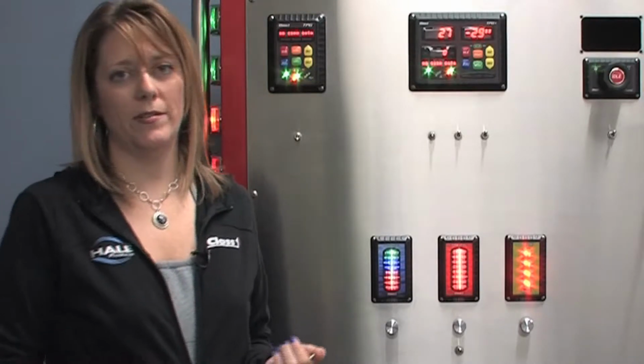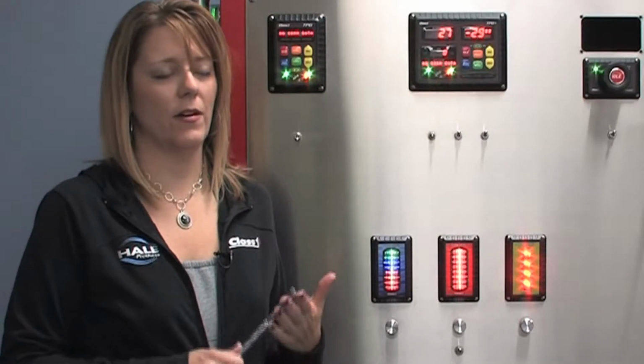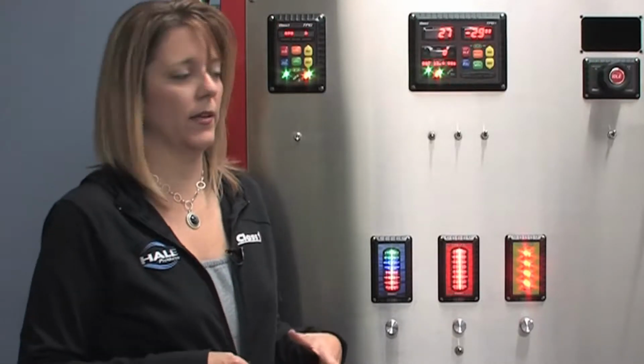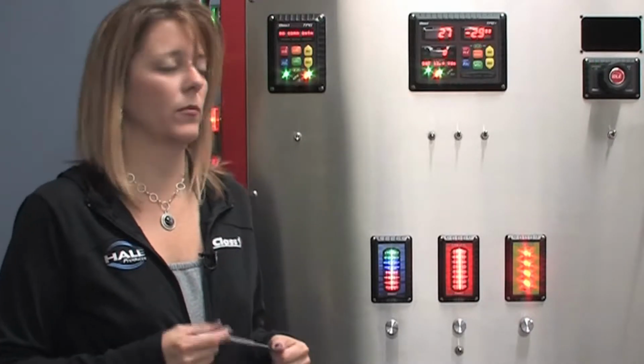The ITL40 can be calibrated in many different ways. We have a 1-point calibration, a 2-point calibration, a 5-point calibration, and a 9-point calibration. The 1-point is the easiest calibration method to use. The 2-point would be the most common. The 5 and 9 should be reserved for odd-shaped tanks. The 5 and 9-point calibration are only as good as the measurement device used to fill the water tank. We highly recommend the 2-point calibration. I'm actually going to walk you through a 1-point and a 2-point, and we'll start with the 1-point.